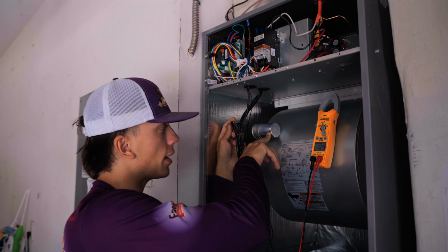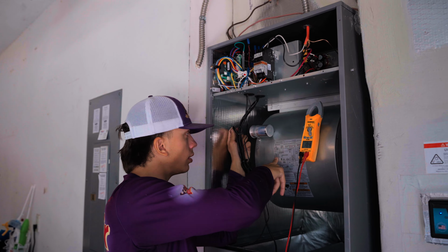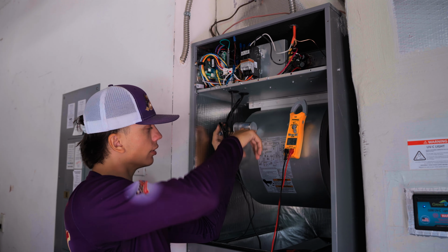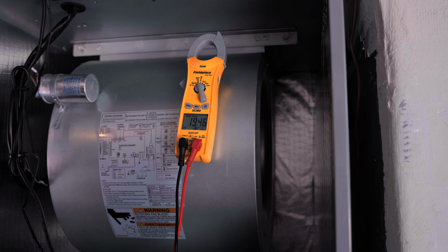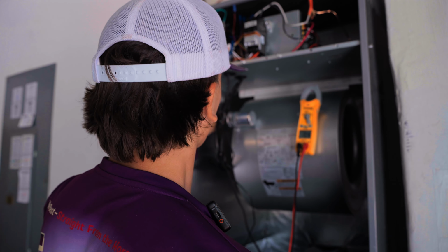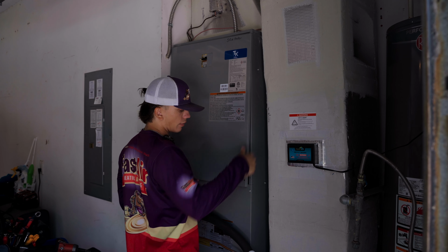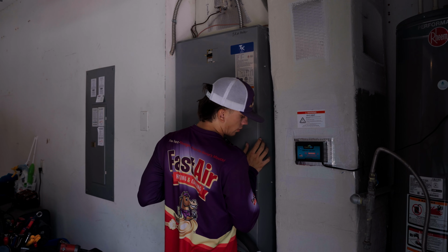So I just checked the capacitor starting component for the blower. It's a 20 microfarad capacitor, and it's reading 19.46, so we know that's good. We're all set in the air handler, just checked everything out, and we're putting the panel back on.